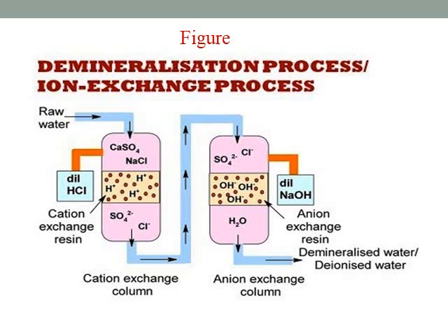As I said, the cation exchanger can exchange all kinds of cations, Na plus, K plus, Ca2 plus, Mg2 plus, etc., which cause the hardness. Once they get exchanged with the exchanger bed, which contains acidic groups, the acidic groups release H plus. So the easily releasable group is H plus. H plus is released into the water, and all the cations are adsorbed on the surface of the exchanger bed. So the water coming after the cation exchanger is free from all kinds of cations, and it only consists of H plus as well as anions.